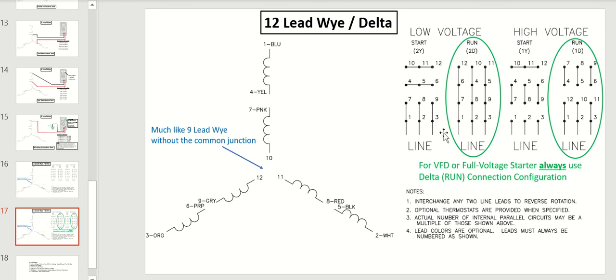But if you're going to use a 12-lead motor for a VFD or some type of full voltage starter where you're putting full voltage on the motor, you always want to connect it in the delta or run connection configuration. This configuration here if it's 230 volt, this configuration here if it's 460 to 480. That always has been a question. You only use the Y configuration for starting, and that's only if you're using what's called a Y delta starter.